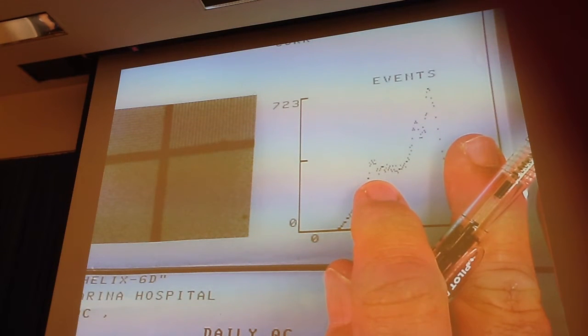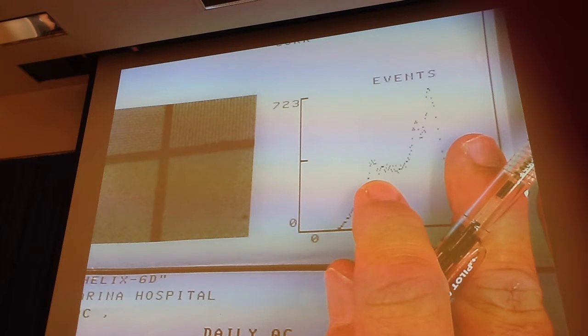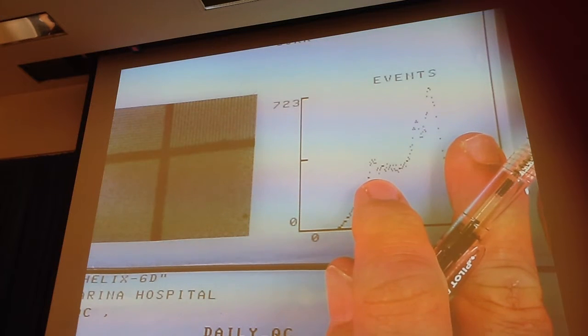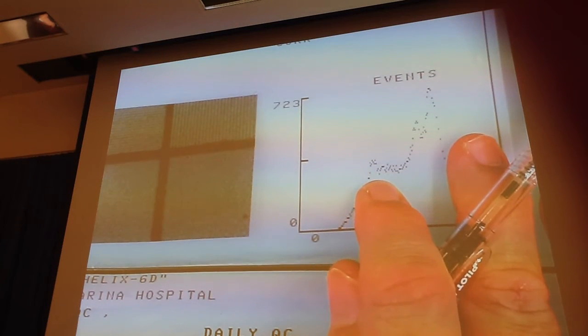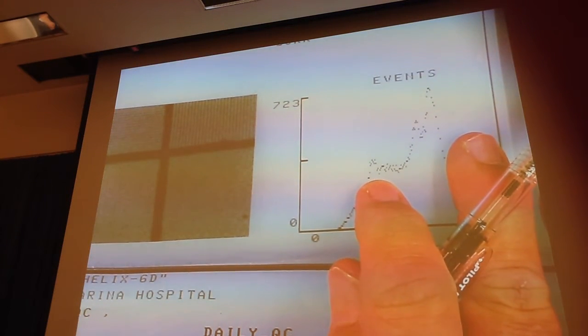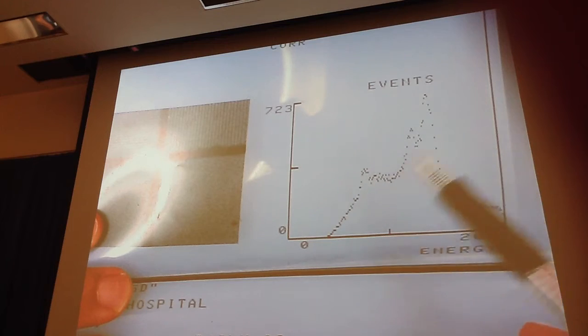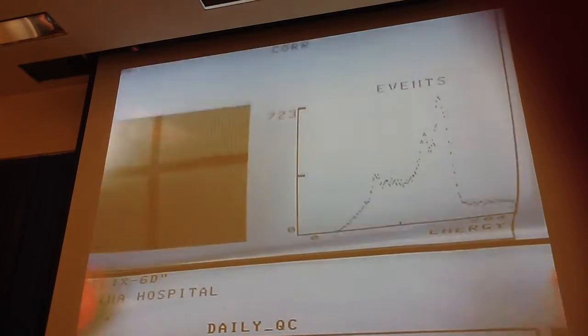And what's good about that is that it is a very sensitive radiation detector, plus it's going to give you a spectrum that tells you what you're dealing with. Okay? So if you're thinking about it once in a while, when the detector head is off, just do a couple of minute acquisition and see if there's any room contamination, because it'll pick it up very nicely and tell you what it is.